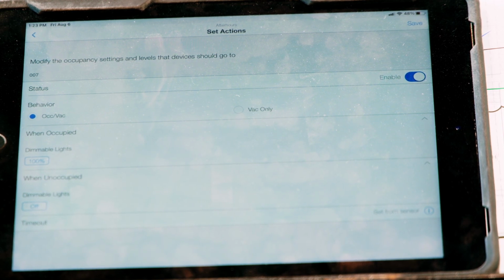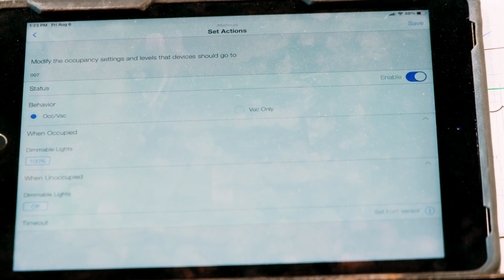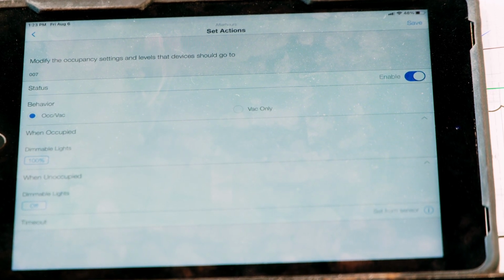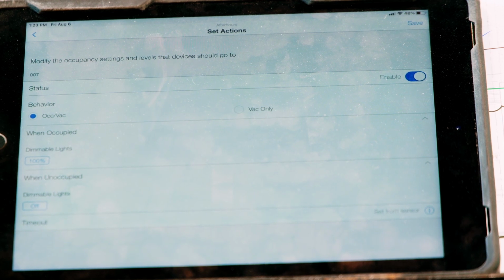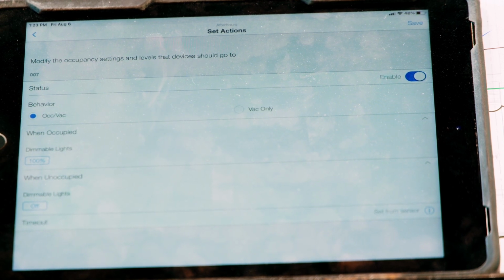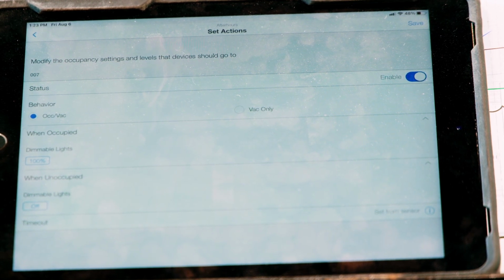One important part that can sometimes be a cause for service calls: the occupancy sensors, the reason why their battery lasts so long is that they only send a signal when they change their state. So when they go from occupied to unoccupied, they send a signal out into the system for the lights to trigger. And then vice versa, when they go from unoccupied to occupied, they send a signal. Otherwise, they're quiet, right? All the occupancy sensors right now from the factory are set for a 15-minute timeout. You can set them to 5 minutes, 15 minutes, or 30 minutes.